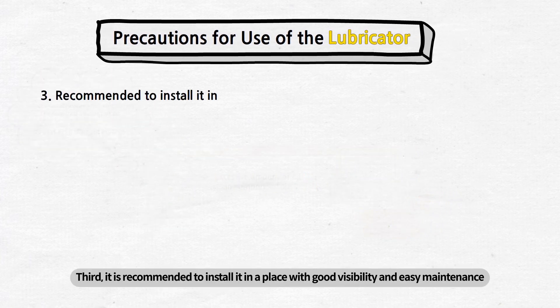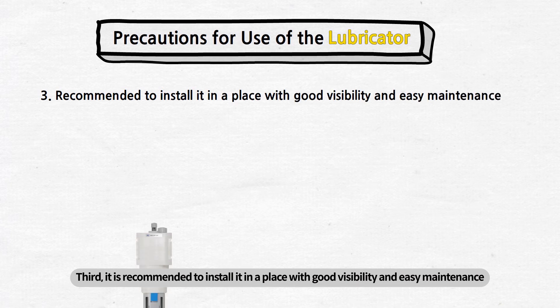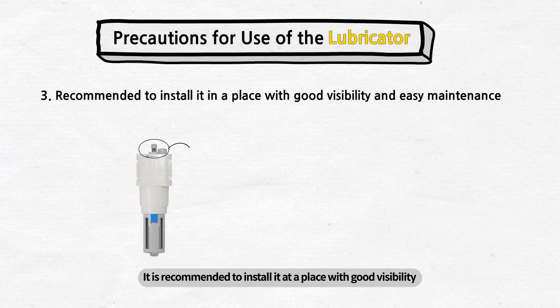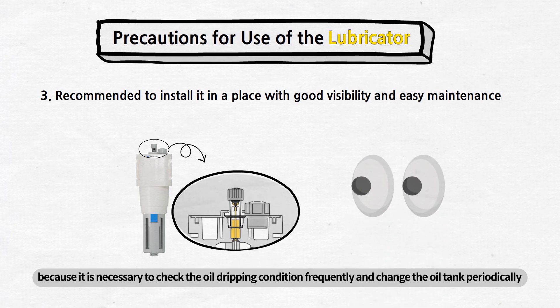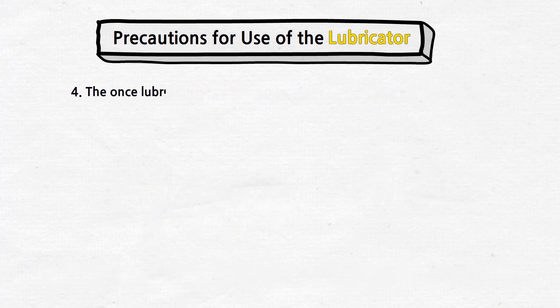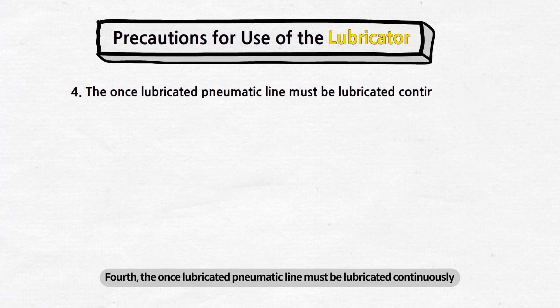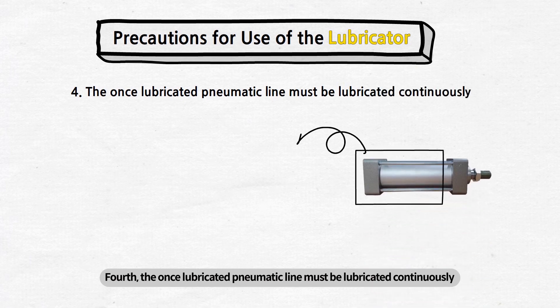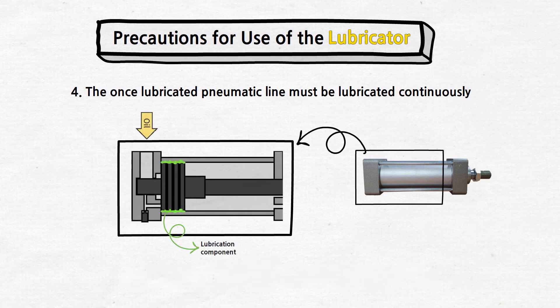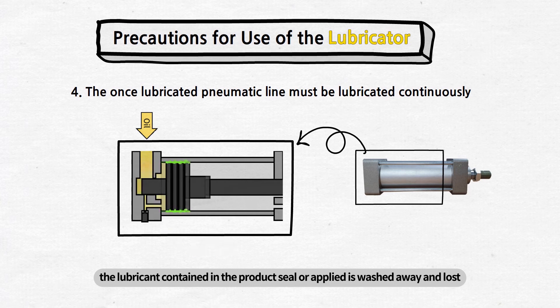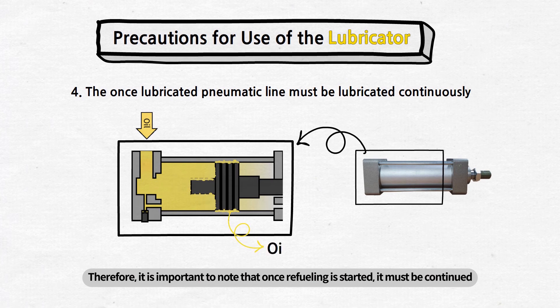Third, it is recommended to install it in a place with good visibility and easy maintenance. It is recommended to install it at a place with good visibility because it is necessary to check the oil dripping condition frequently and change the oil tank periodically. Fourth, the once lubricated pneumatic line must be lubricated continuously. When lubricating the valve or cylinder by installing the lubricator, the lubricant contained in the product seal or applied is washed away and lost. Therefore, it is important to note that once lubrication is started, it must be continued.